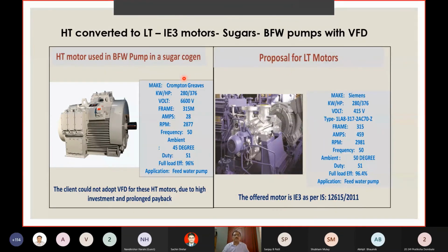So we helped one industry wanted to go for a LT motor with VFD, boiler feed pump, because they were able to see that their HT motors were operated with the valve closed condition most of the time throughout the year crushing season. So they came forward, 3 of their pumps were replaced with LT motors, and in 2 crushing seasons, motor with VFD, they were able to recover the cost of investment. So I'm just showing only case studies where we had very big successes. So conversion of a medium voltage motor to an LT voltage motor is also a possibility which you can consider for people who are coming from that part of the country where sugar is a very popular application area. I thought I will include this slide.